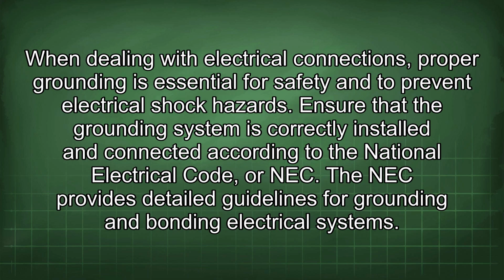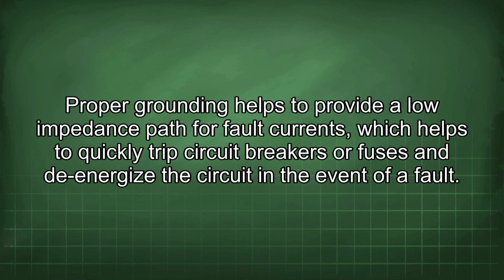When dealing with electrical connections, proper grounding is essential for safety and to prevent electrical shock hazards. Ensure that the grounding system is correctly installed and connected according to the National Electrical Code, or NEC. The NEC provides detailed guidelines for grounding and bonding electrical systems. Proper grounding helps to provide a low impedance path for fault currents, which helps to quickly trip circuit breakers or fuses and to de-energize the circuit in the event of a fault.